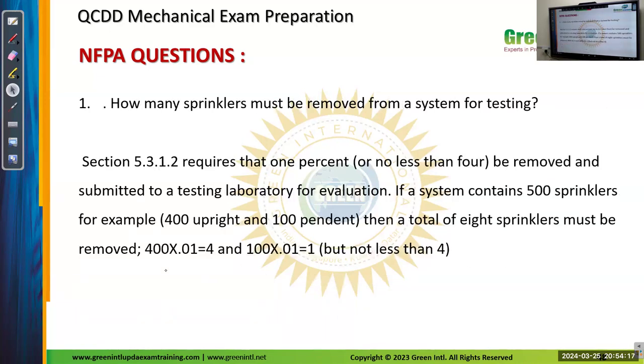So how many sprinklers must be removed for testing? This question they have asked. How many sprinklers must be removed from a system for testing? It requires 1% or no less than 4 to be removed and submitted to a testing laboratory for evaluation. If the system contains 500 sprinklers, for example, 400 upright and 100 pendant, then a total of 8 sprinklers must be removed.